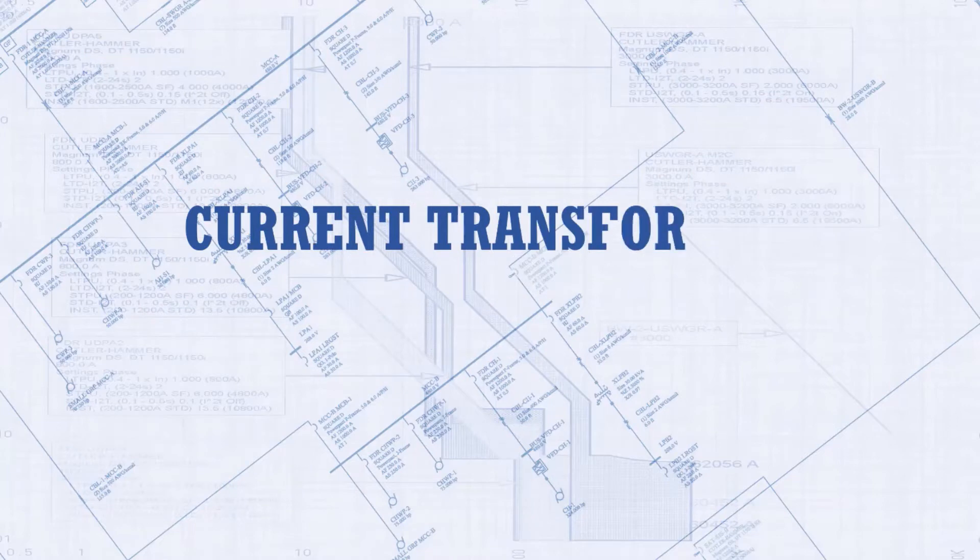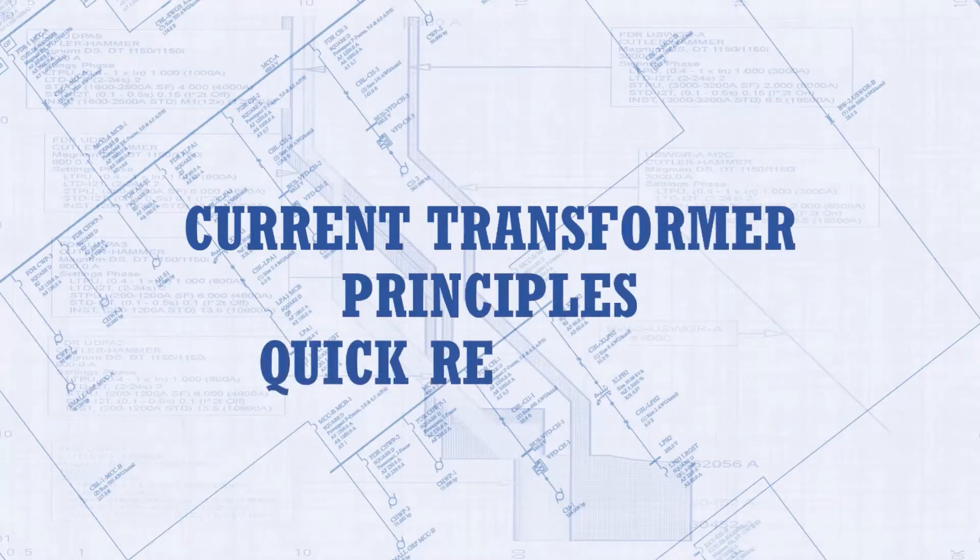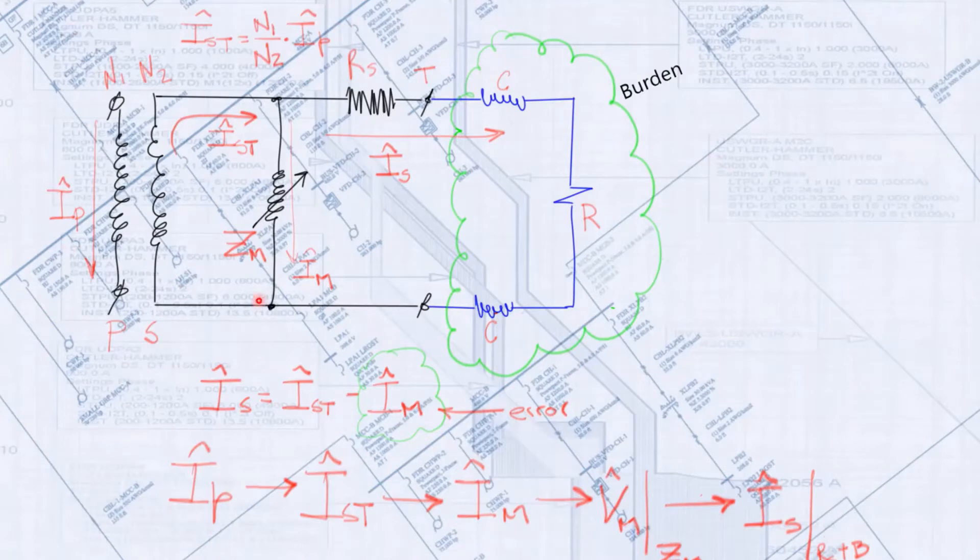First, a quick refresher on current transformer principles of operation. This is the basic steady-state equivalent circuit of a CT. A primary winding and current, the secondary winding and total secondary current, the CT ratio relating primary and ideal secondary currents, and the magnetizing impedance of the CT which defines a saturation characteristic.